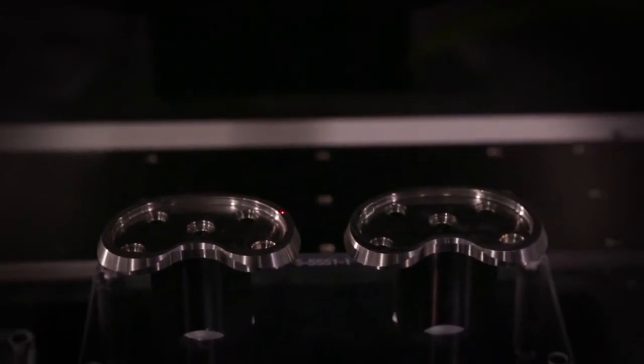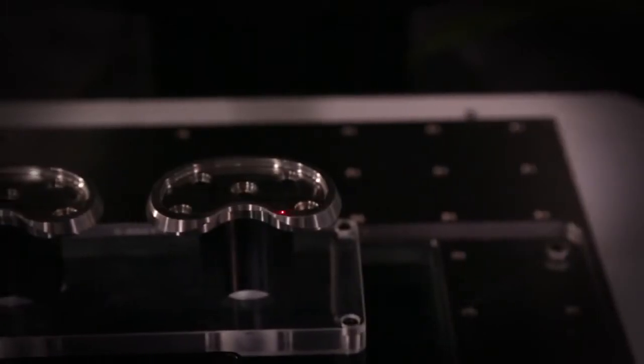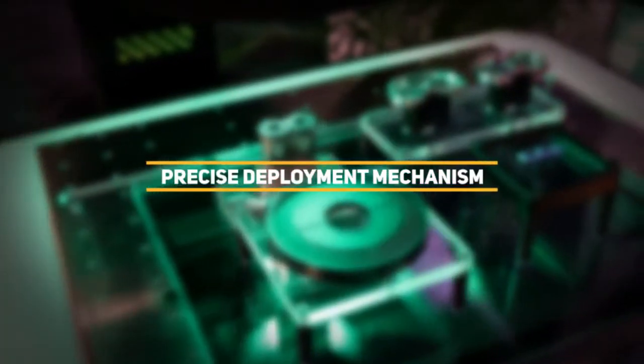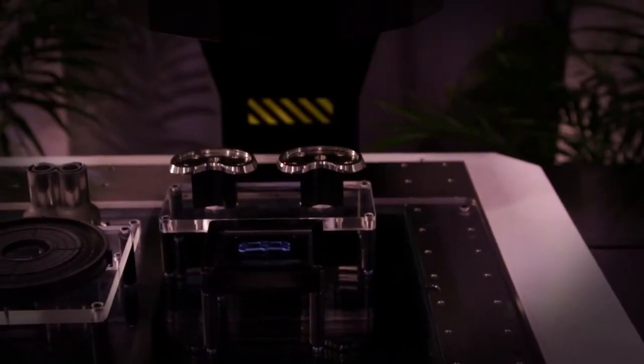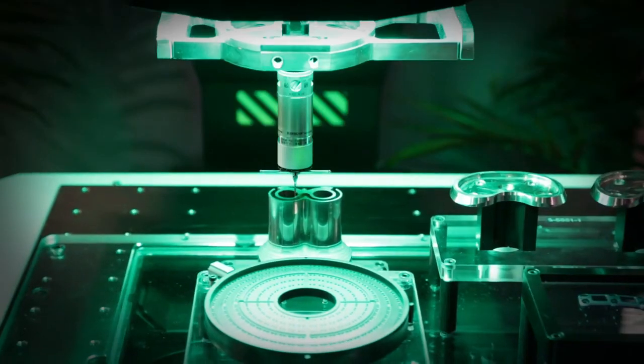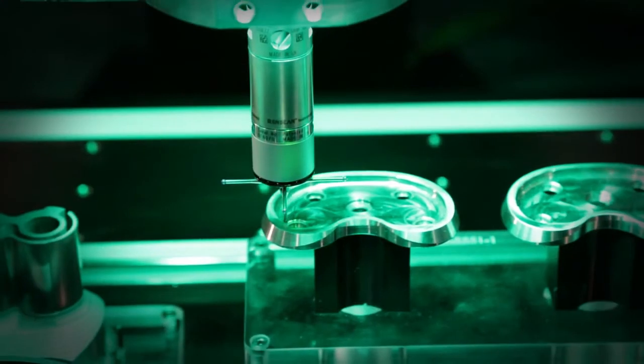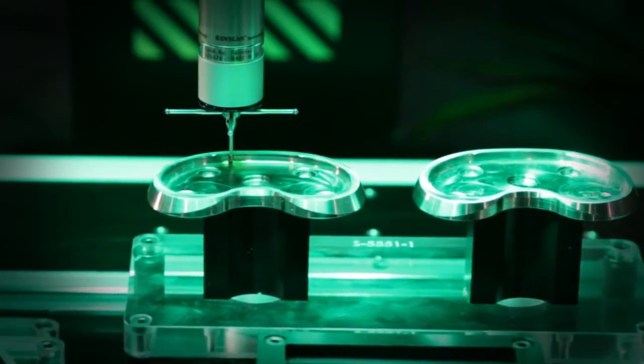Since the laser goes through the optical system, they're not offset by the optics, meaning parts that span the entire stage can be measured. This is also the case with tactile sensors. With the Fusion, it's possible for optics, touch probes, and scan probes to all occupy the same space. This is made possible by the Fusion's precise positional rotational deployment mechanism, which can bring bulky sensors into the measurement area when needed and then remove them when finished. This gives the Fusion the ability for scanning probes to reach internal features on parts which video and laser sensors may not be able to access.